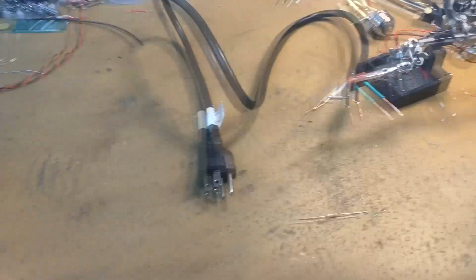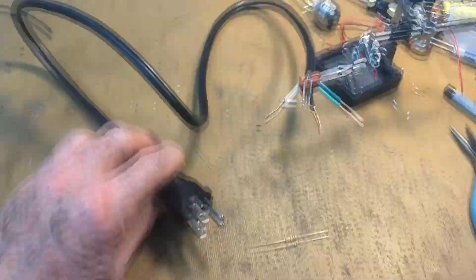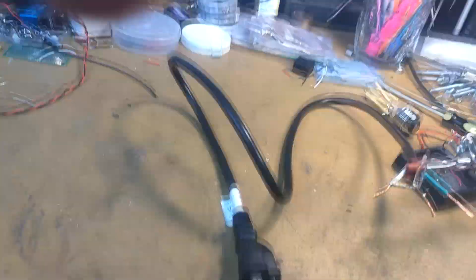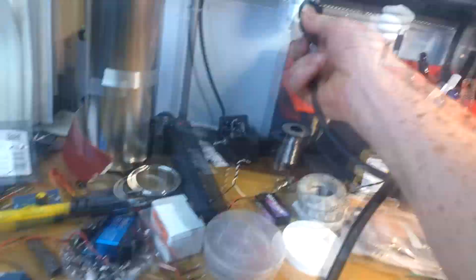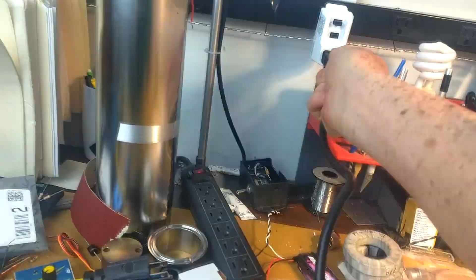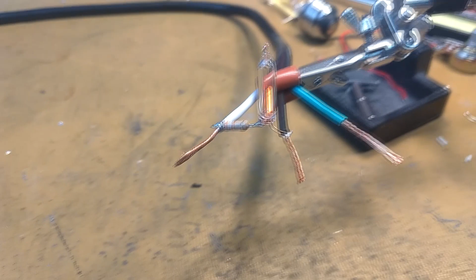This is an ordinary 3-conductor power cord, and I've stripped the ends here, and I've connected a neon lamp through a 47K ohm resistor between the hot lead and the neutral lead. And of course this is the ground lead. I'm going to plug this in to our ground fault circuit interrupter and reset the device.